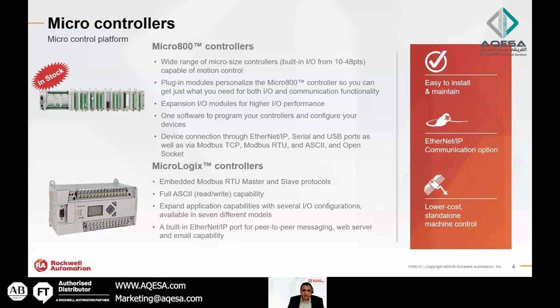It has plug-ins and expansion modules to increase IOs. One software, Connected Components Workbench, develops the whole family. It has a lot of communication support: Ethernet, serial, USB, Modbus TCP, Modbus RTU, ASCII. You can even use gateways for other communications to Ethernet or Modbus. It can communicate with VFDs, motion controllers, everything over Modbus or Ethernet.